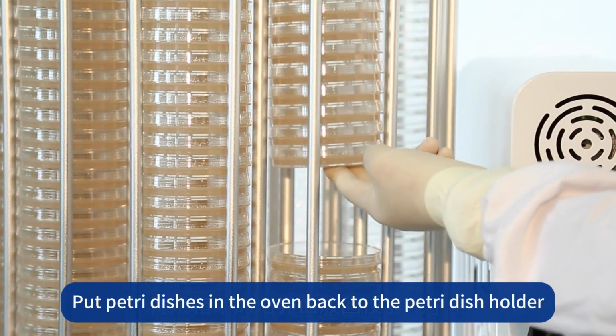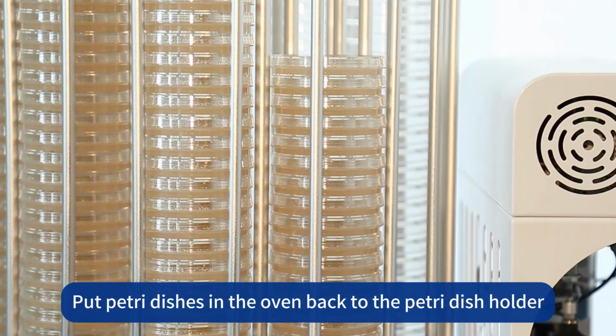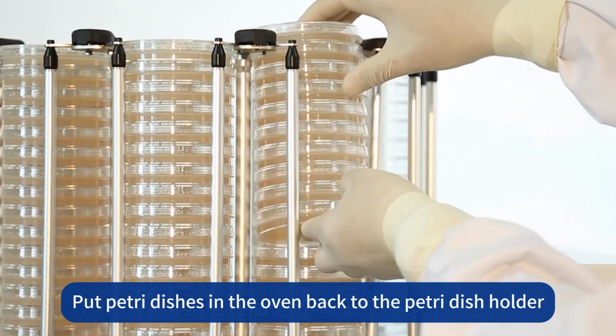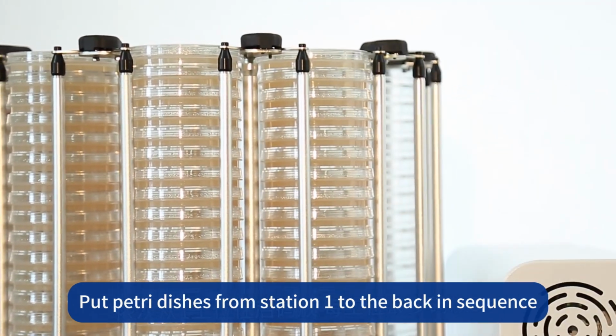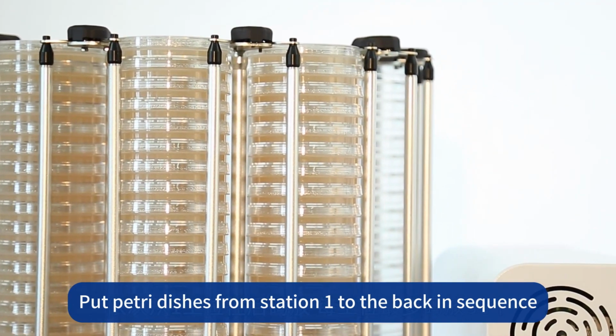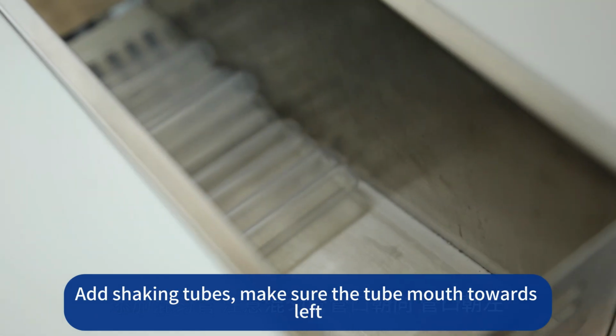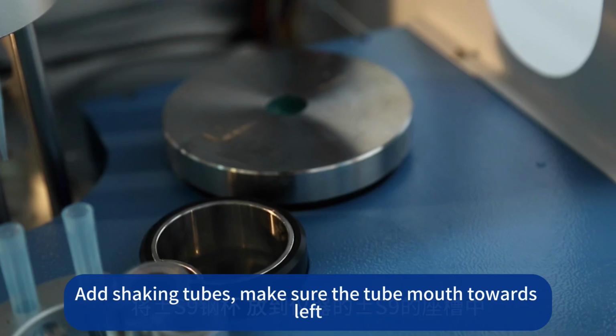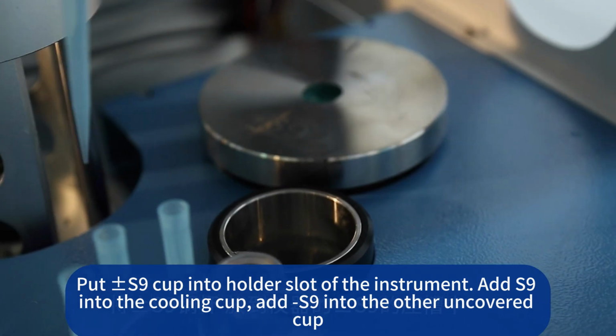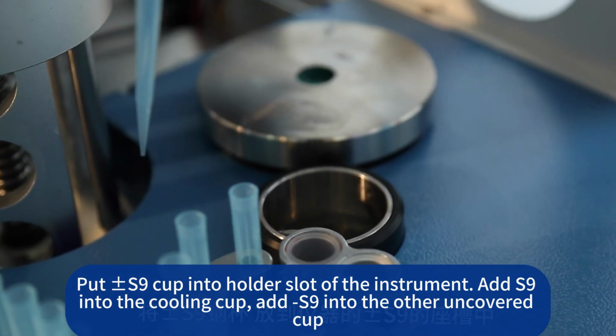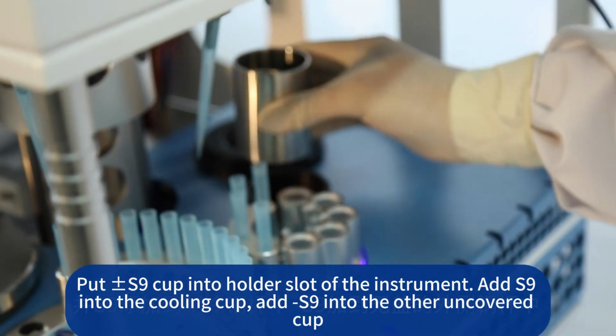Put Petri dishes in the oven back to the Petri dish holder. Put Petri dishes from station 1 to the back in sequence. Add shaking tubes, make sure the tube mouth towards left. Put plus or minus S9 cup into holder slot of the instrument.